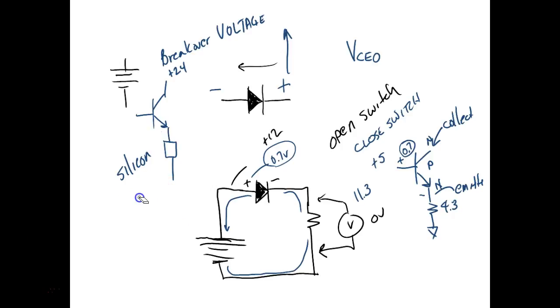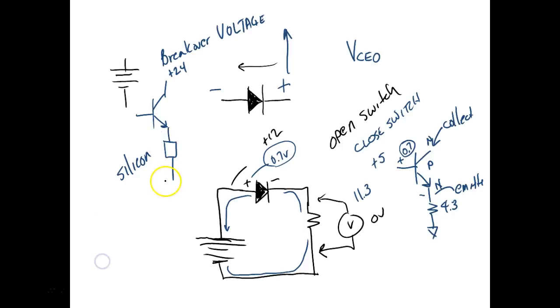And these are the 1200s. So the 1200s are sourcing outputs. So what that means, if it's DC, we're outputting on a transistor. If something happens on this load right here, or something happens to the 24 volts and I see the breakover, that's not our problem. The problem is this load.